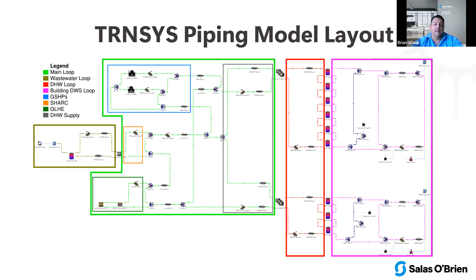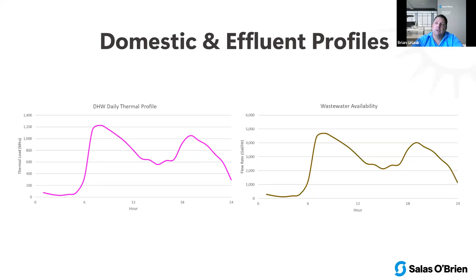So a few things that we have to put into the program. Obviously, you need to know your daily domestic hot water and wastewater availability. That's critical to sewage heat recovery, right? We need to know what that looks like. Again, there's a lot of information out there. New York City, from what I understand, what we were modeling initially was not close because even though they have occupancy codes, they tend to put more people in these buildings due to rent costs than what you're actually by code designing to. So we did a lot of sensitivity there and looked at that.